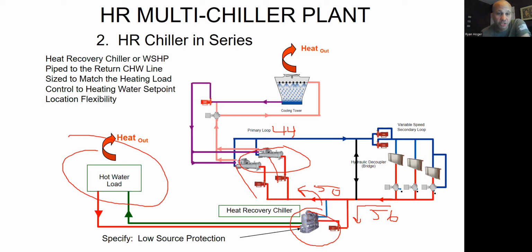So you can do this with a chiller or a water source heat pump. Once again, these big chillers are really just water source heat pumps. You will seldom find them labeled that way because the manufacturers of chillers and the engineers that work on chillers are very prideful individuals, and they don't want to consider themselves to be anything other than a chiller. They're a chiller, right? We just found a way to use our chiller to heat your building. So it's still a water source heat pump. It's just a really big one. Sorry, I didn't mean to swear. But they're probably going to be labeled and marketed and sold as heat recovery chillers or heat reclaim chillers, but they are in fact the same thing as a water source heat pump.